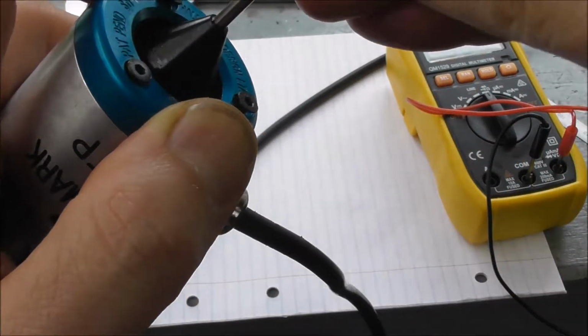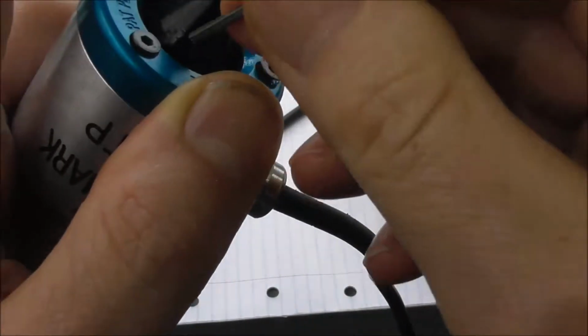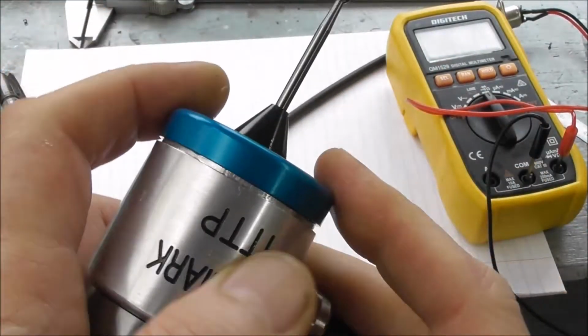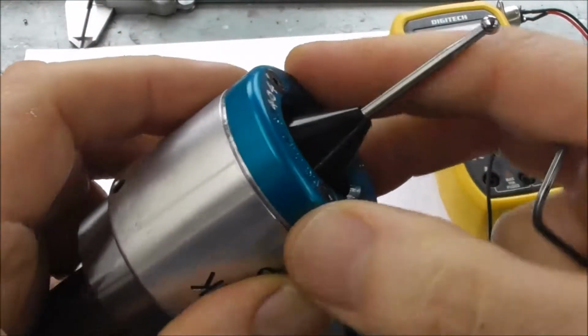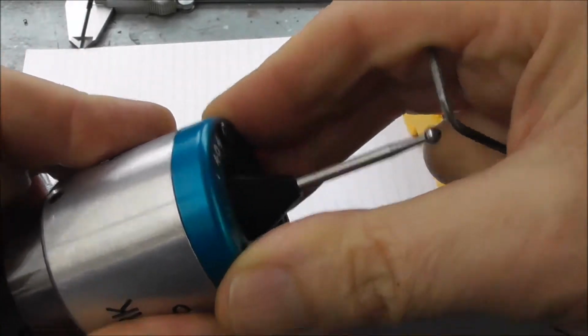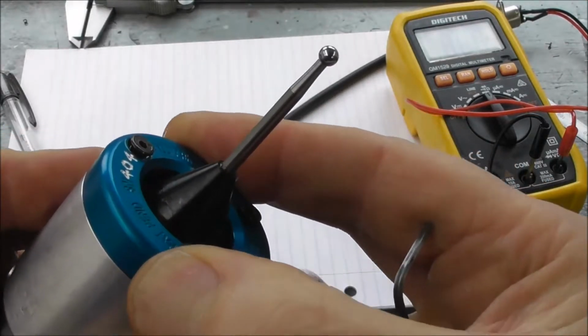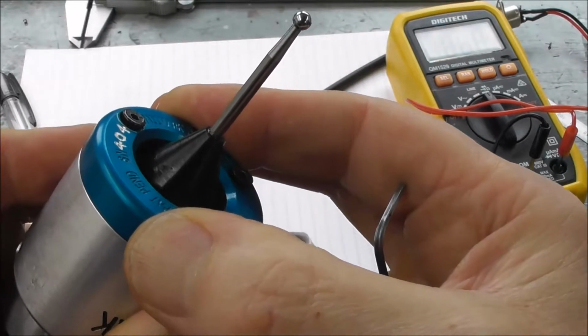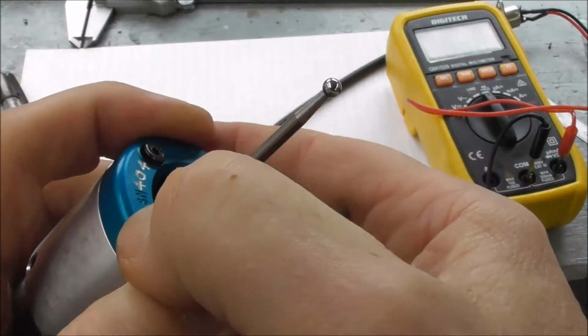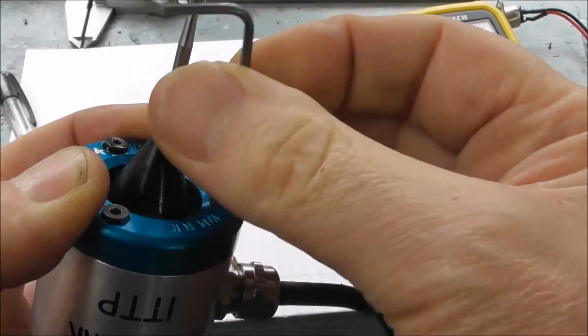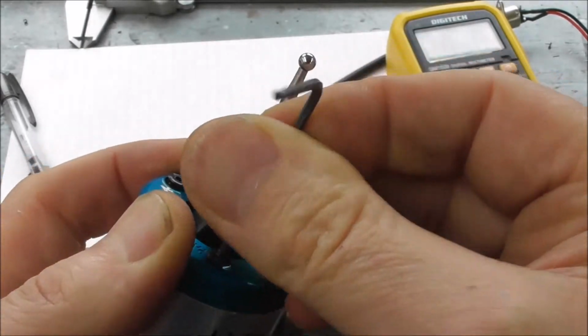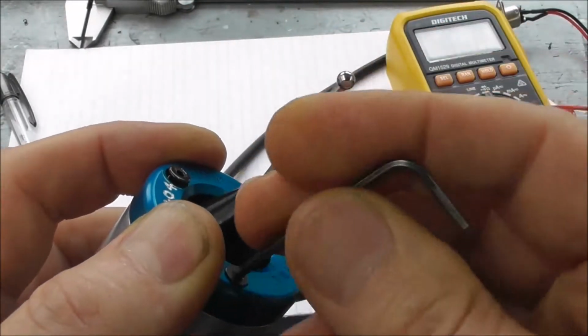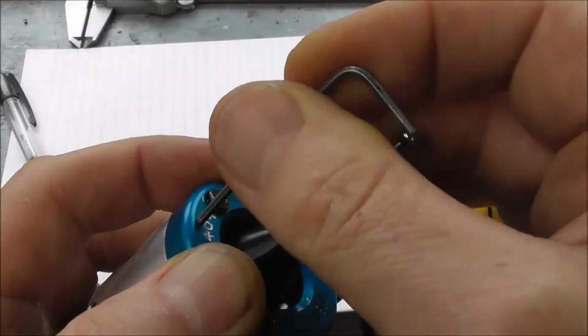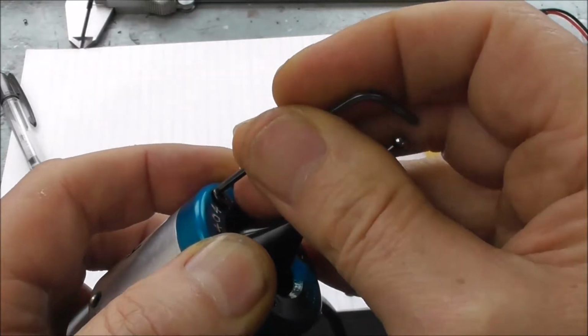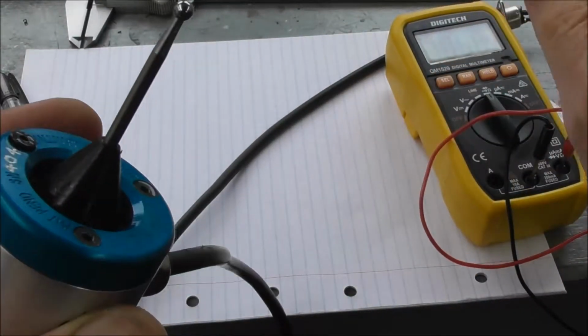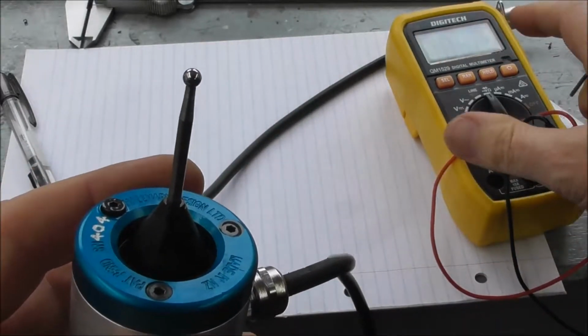What you can do is loosen all the cap screws, just enough so that the heads are out of their countersinks, like that. So you've got this looseness, push it in and then just rattle it within the clearance of the cap screws, and that may well cause the spring-loaded pogo pins to ride over a little piece of grease or fluff that's got in there, and you can hear it audibly come right if there's a little connection problem. I mean, really ideally you should fully dismantle it and wash it out with kerosene and blow it off with compressed air, but if you just want a quick fix to get it going for a job, you could try that.